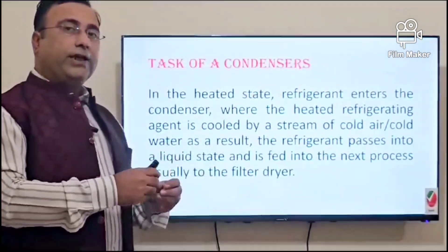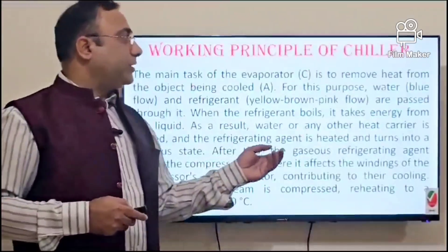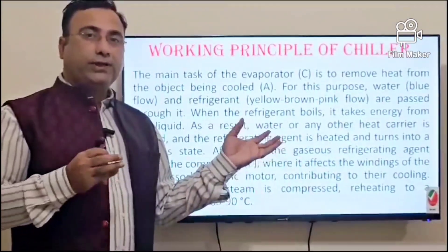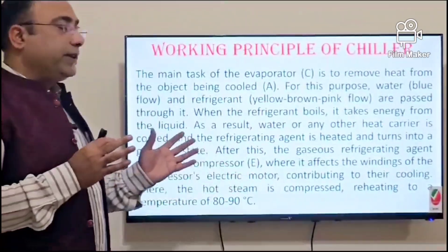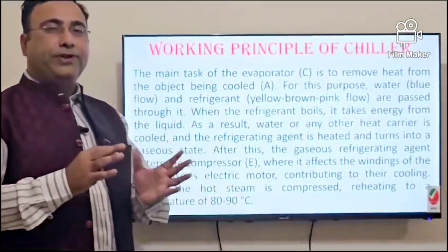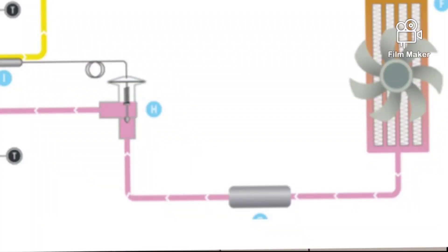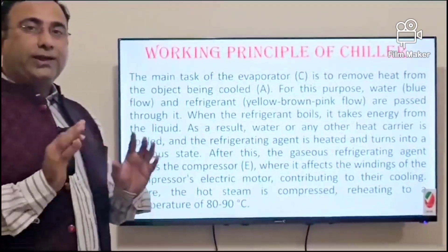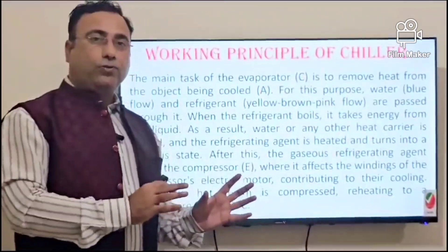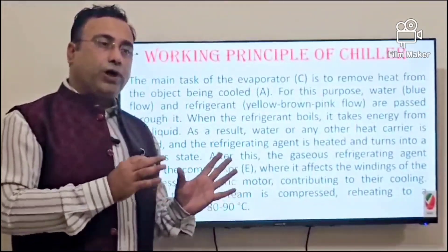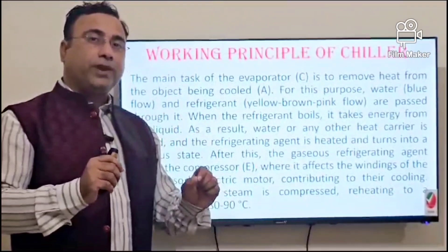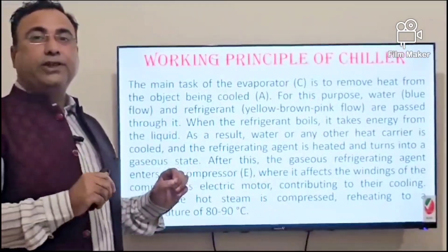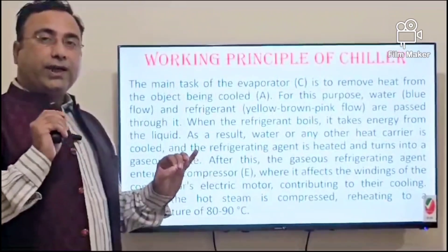After the condenser, the refrigerant passes into a liquid state and goes to the next process. If the capacity is more than 10 TR, the chiller company usually provides a dryer; below that, only a filter is used. The dryer removes humidity from the outer piping — it has no relation to the water or oil you want to cool. The system is 100% sealed internally with no chance of leakage.